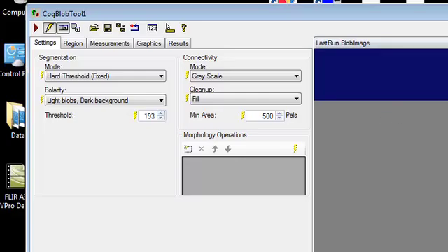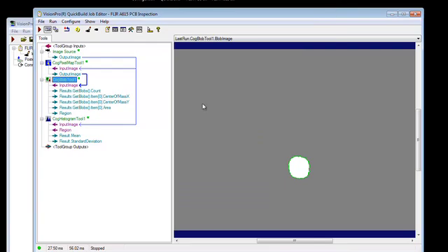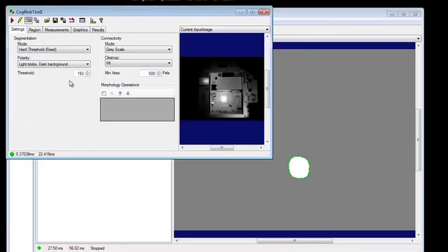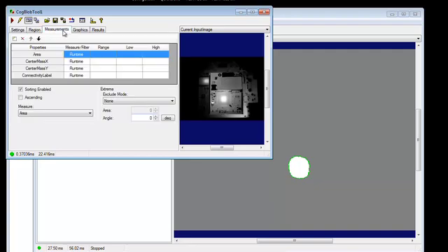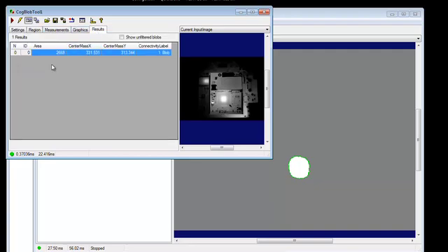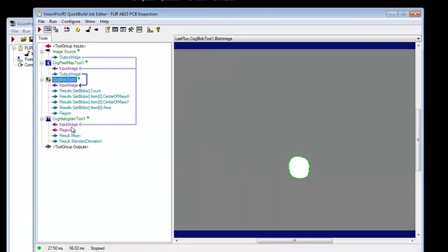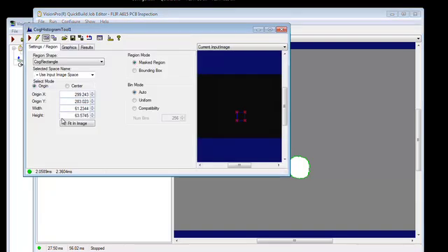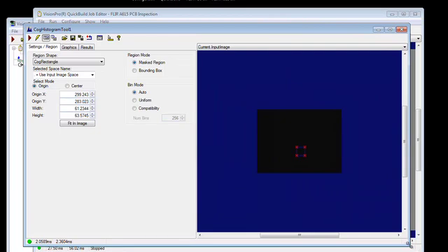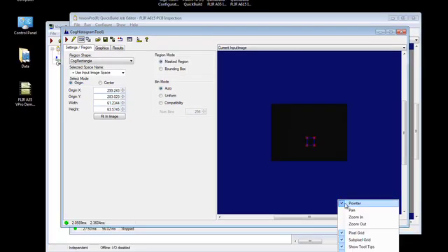So as we adjust the size and as we adjust our threshold for our 8-bit linear value on our temperature, we can find a blob area that we want to see. So we've set our threshold, we've selected our blob, and based upon our blob you can also see several data points that are available in the results table. So we found one blob of a given area, center mass for X and Y, so that you know where your blob is and how large it is. But what's really important about this blob analysis that we are doing here is not only the blob analysis, but we want to know what the temperature value is for a given region of interest.